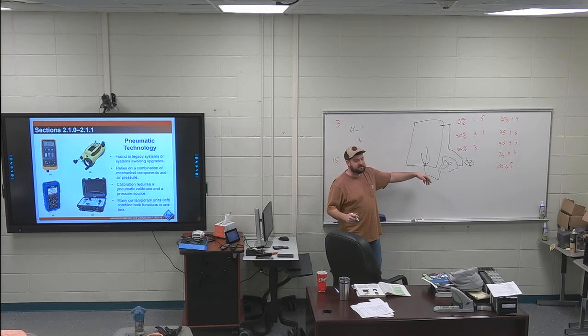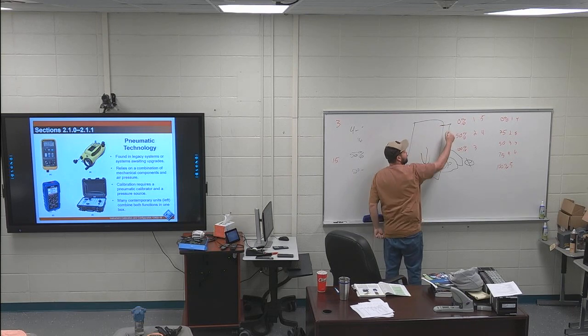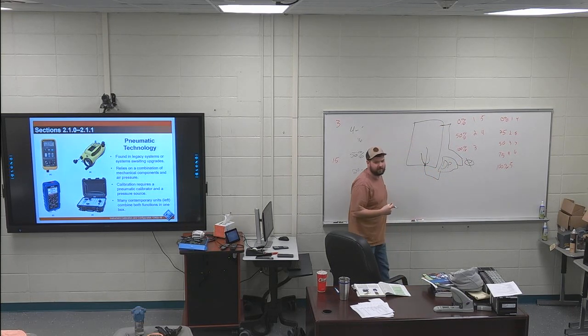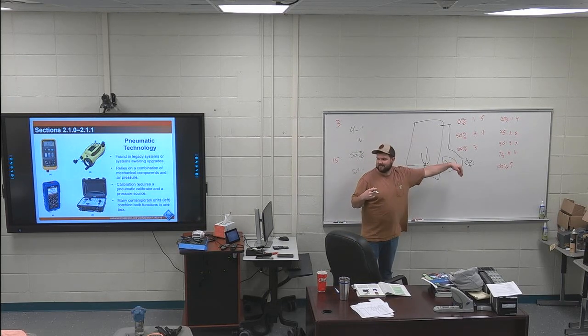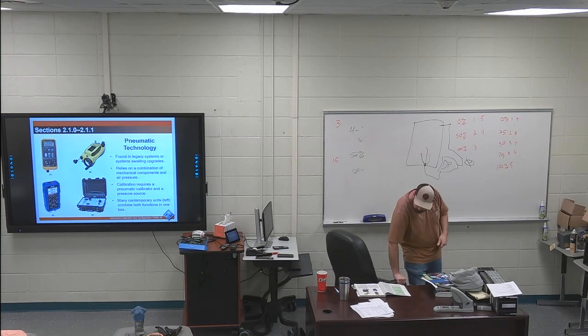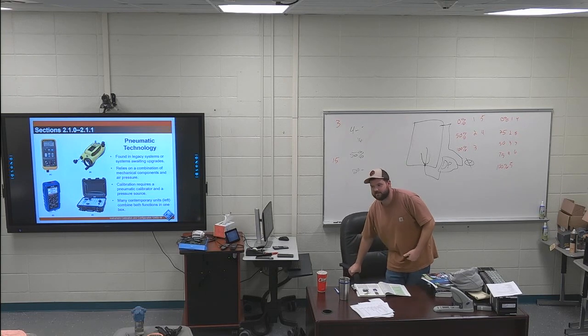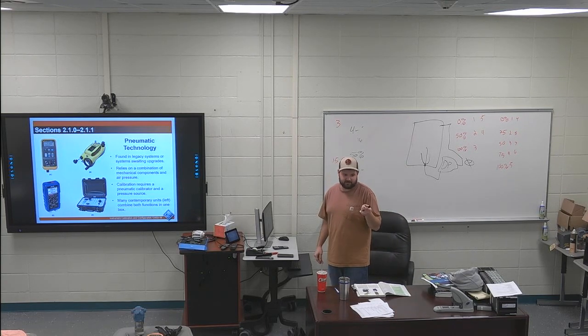So if that happens, they fill this whole leg with an inert fluid or something like that, and it's called a wet leg. And they fill it up, and then they set that side to 0. Does that make sense? So you can have a dry leg or a wet leg. You can also have a suppressed 0. So you messed with that last semester. Remember how you had to put in like negative 4.1 or 3.6?